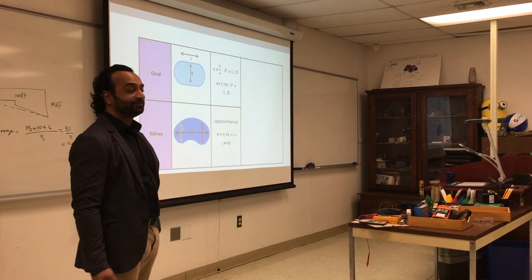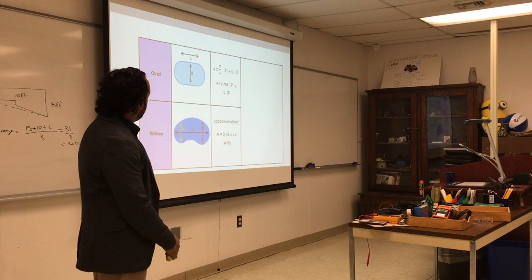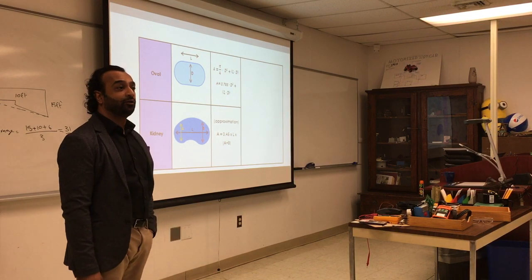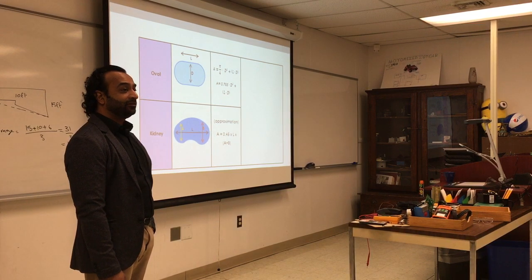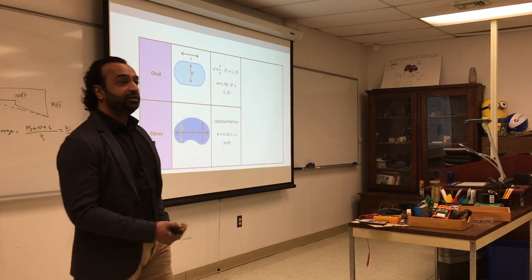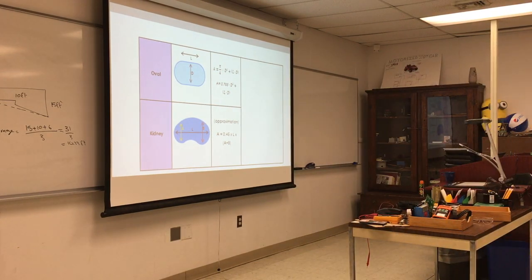So every time you have a different shape, you have a different factor and a different volume. I'm trying to calculate the volume because I'm heating the water. Calculate the volume and the surface area. I need the surface area because the surface area will tell me how much heat I'm losing, and the volume will tell me how much heat I need to put in.